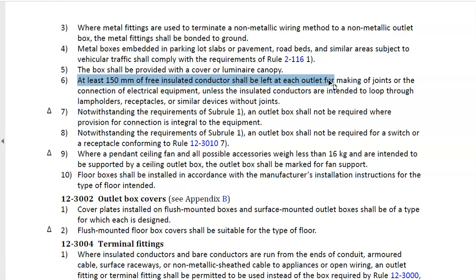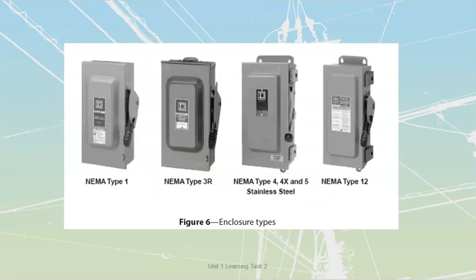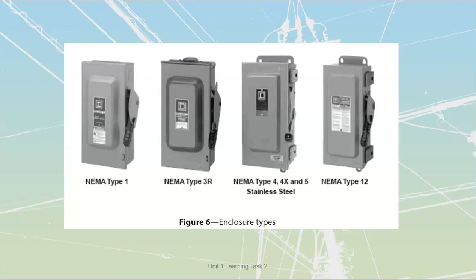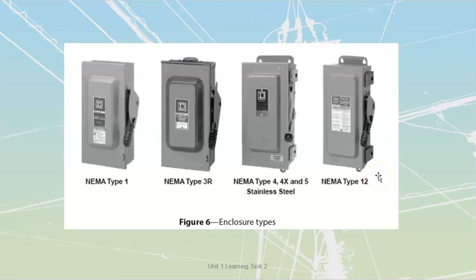Now let's talk about environmental characteristics. We have different NEMA classifications for switches: Type 1, 3R, 4, 4X, 5, and NEMA 12, which are increasingly robust and sealed against environmental ingress. NEMA 1 enclosures have knockouts, while weatherproof types require threading in through hubs, and in many cases the category requires entry only from the bottom. When working with weatherproof equipment, always come up from the bottom rather than down from the top — it's much easier to drain water out than to try to stop it from getting in.